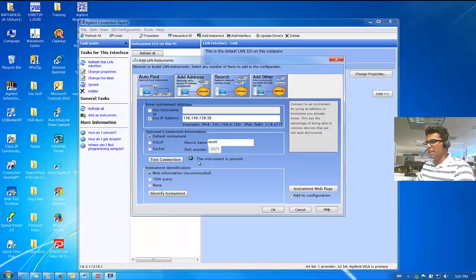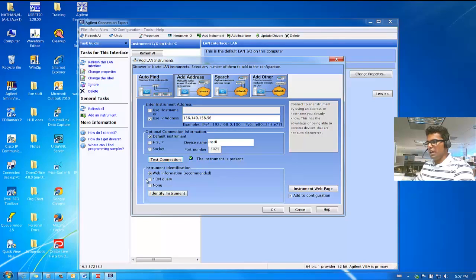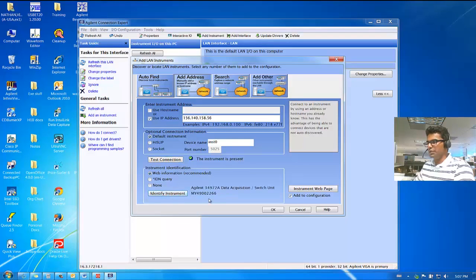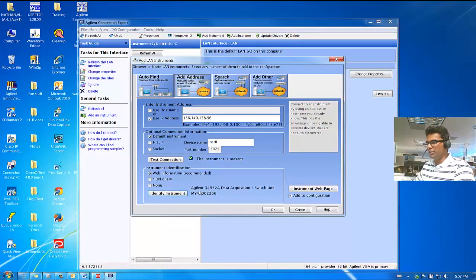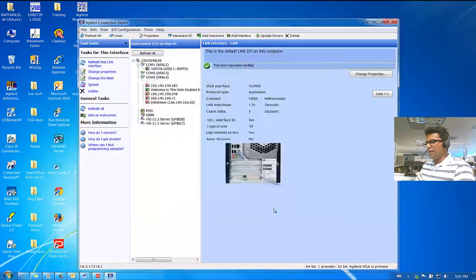Test the connection first. It shows that the instrument is present. And then you can click on Identify Instrument. And as you can see, the 34972A is a newer instrument, so it shows up as Agilent. Click OK.